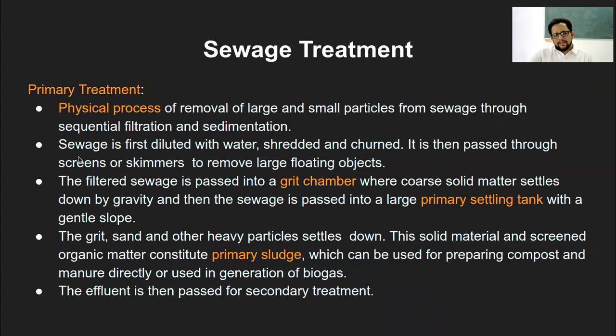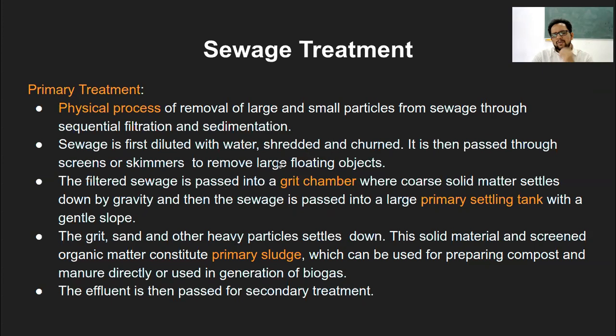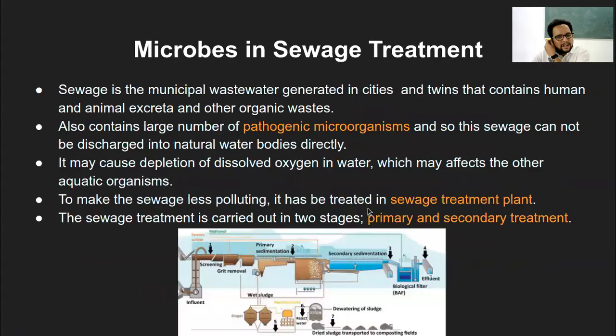The first step is the sewage is diluted with water, shredded, and churned, then passed through screens or skimmers to remove large floating objects and maximum possible solid particles. The filtered sewage is then passed through the grit chamber - grit refers to the solid mass left behind after the first filtration unit. In the grit chamber, coarse solid matter settles down by gravity, and then the sewage is passed into the large primary settling tank.